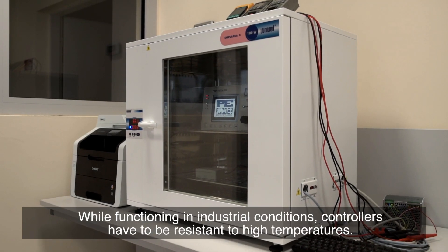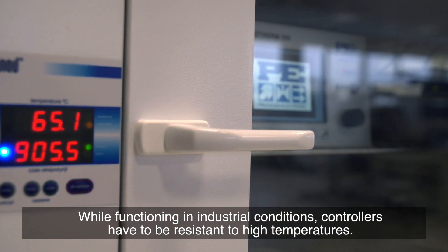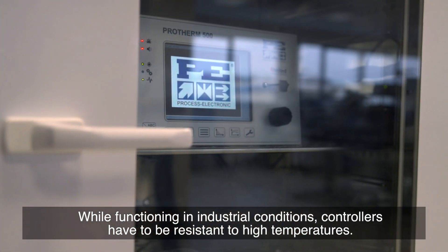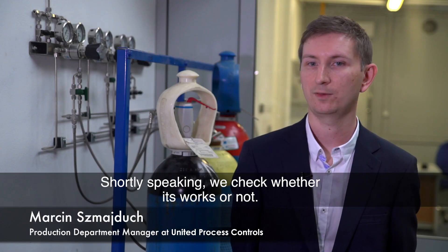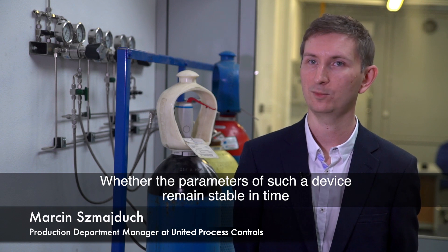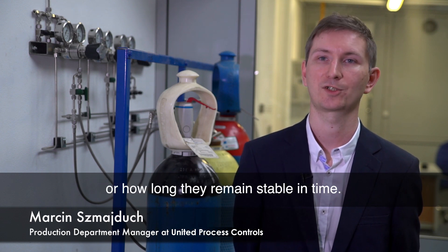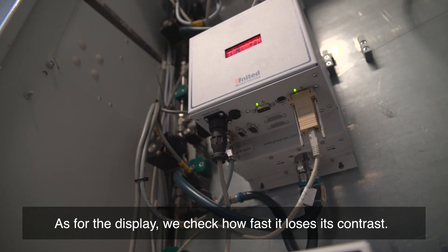Another stage consists of thermal tests. While functioning in industrial conditions, controllers have to be resistant to high temperatures. We check whether the parameters of such a device remain stable in time, or how long they remain stable in time. As for the display, we check how fast it loses its contrast.